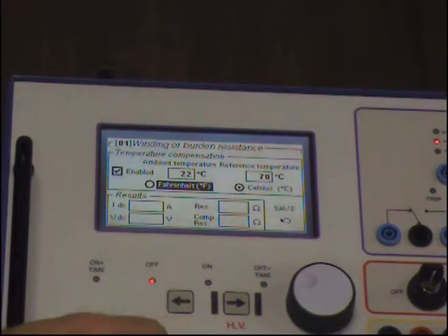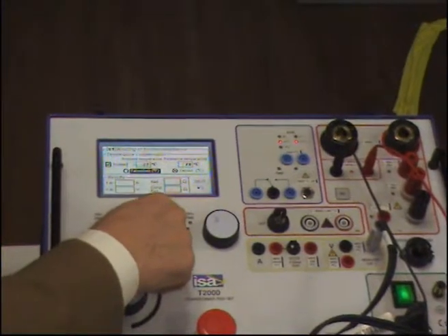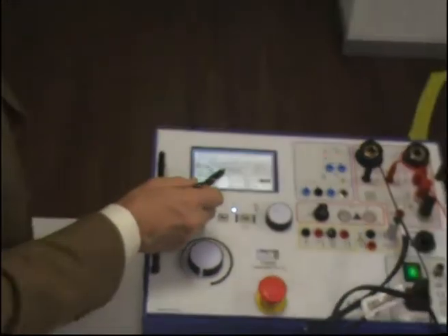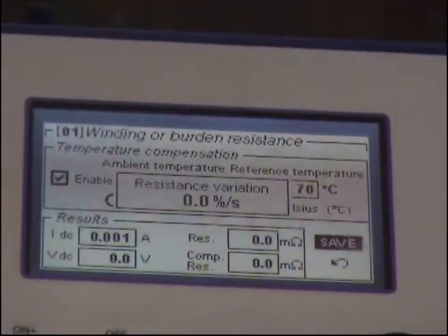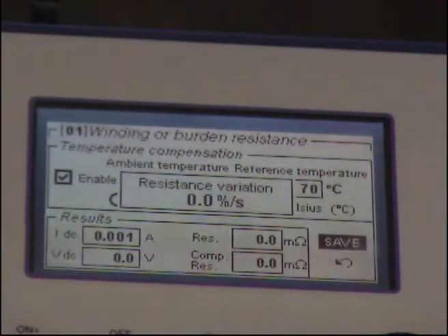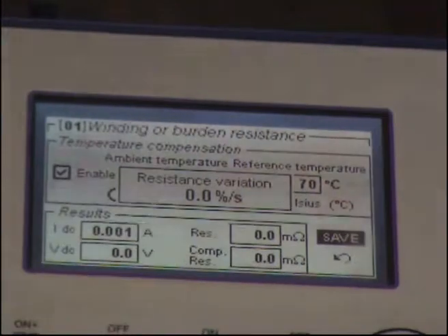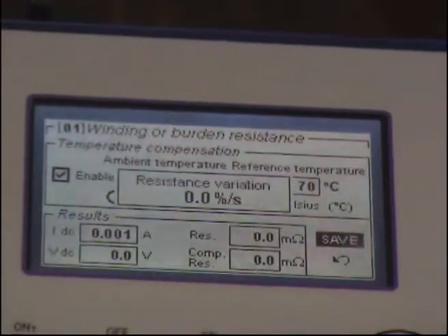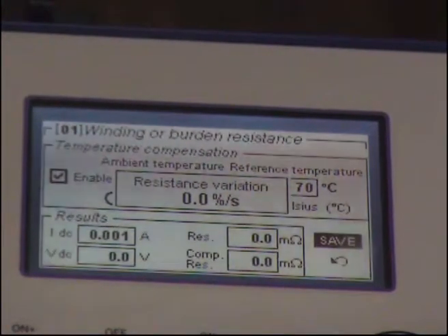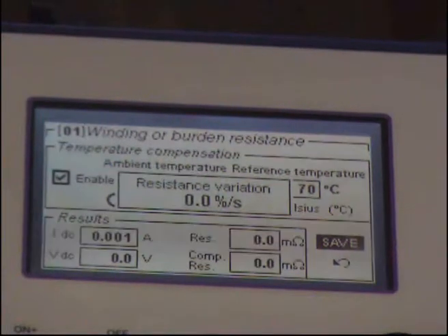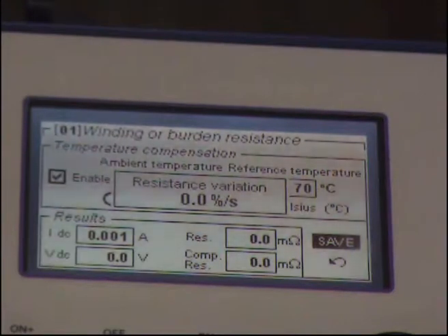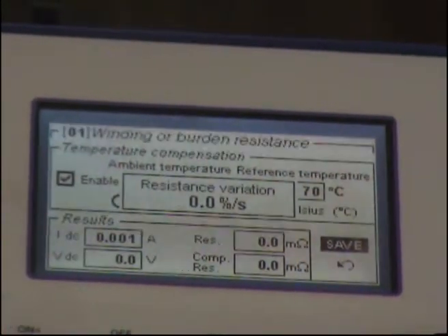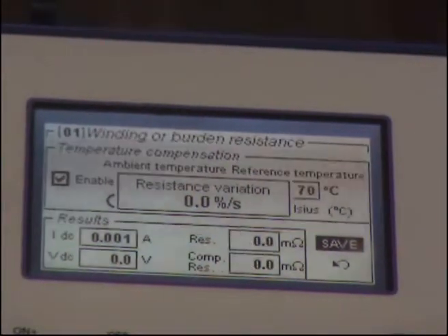Now, it's done. I repeat, what we do is to apply a DC current into the secondary of the current transformer. You see, resistance variation, what is it for? It is because the current transformer, all transformers, will have an inductance. And by the way, this inductance in big transformers is so big that you are close to being unable to perform the test. Anyway, with big transformers, the way to improve the situation is to short circuit all other windings except the one that you are testing. Now, this is a small current transformer, so I don't do anything. Otherwise, I should short-circuit the primary side.